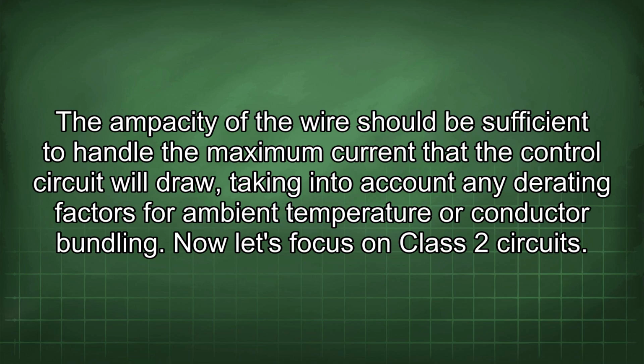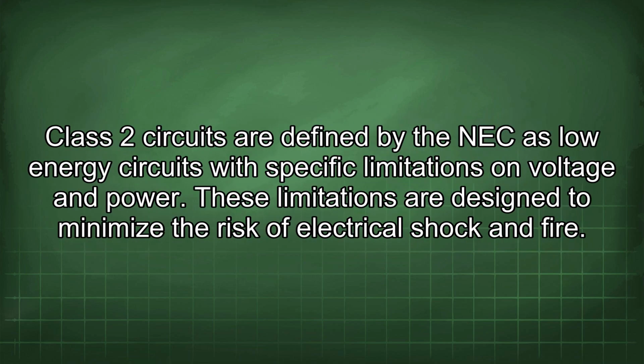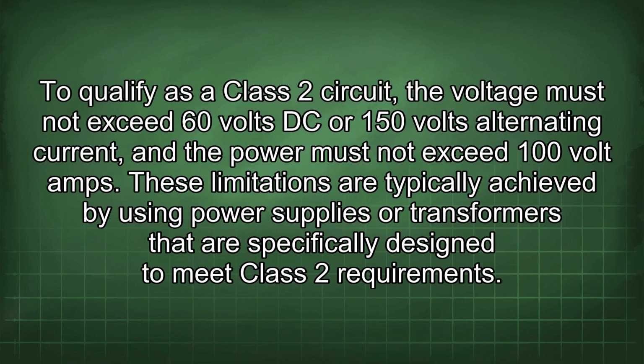Now let's focus on Class 2 circuits. Class 2 circuits are defined by the NEC as low-energy circuits with specific limitations on voltage and power. These limitations are designed to minimize the risk of electrical shock and fire. To qualify as a Class 2 circuit, the voltage must not exceed 60 volts DC or 150 volts alternating current, and the power must not exceed 100 volt-amps.